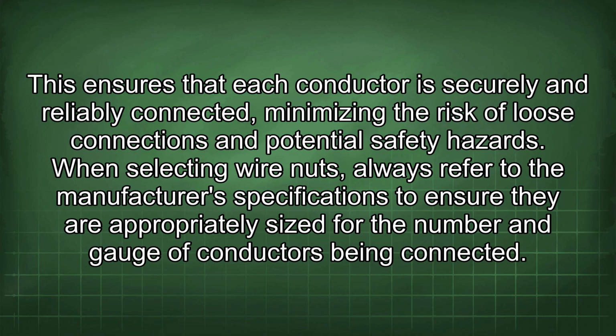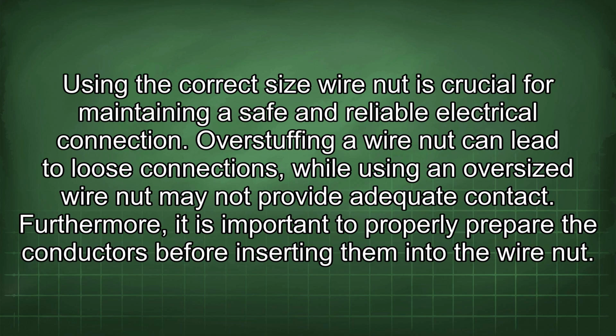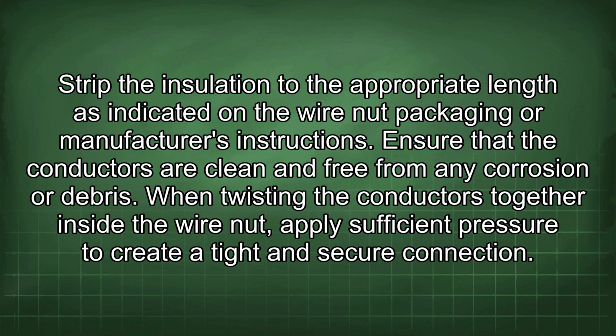When selecting wire nuts, always refer to the manufacturer's specifications to ensure they are appropriately sized for the number and gauge of conductors being connected. Using the correct size wire nut is crucial for maintaining a safe and reliable electrical connection. Overstuffing a wire nut can lead to loose connections, while using an oversized wire nut may not provide adequate contact. Furthermore, it is important to properly prepare the conductors before inserting them into the wire nut. Strip the insulation to the appropriate length as indicated on the wire nut packaging or manufacturer's instructions. Ensure that the conductors are clean and free from any corrosion or debris.